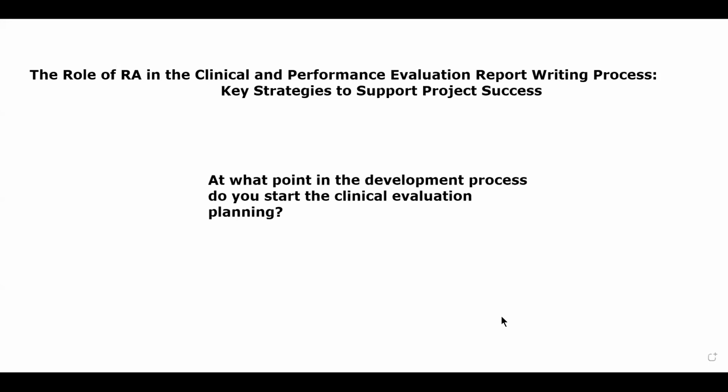So keep in mind when you're making these early decisions, develop the clinical data for it, not just the technical data, but how are you going to get your clinical data for that intended use that you're contemplating? What claims are you prepared to write down? And do you have the clinical data for them if those claims lead to a clinical patient benefit? So this is, again, getting back into some of these, like Article 61(10), which was really what I was referencing right there.